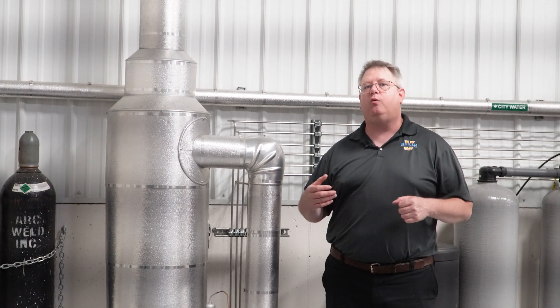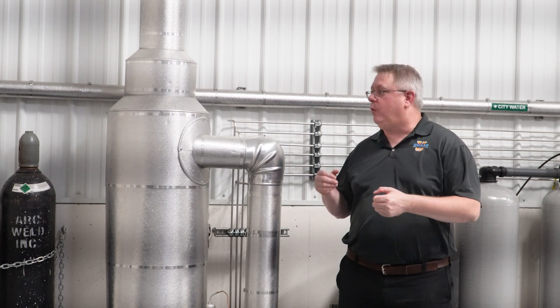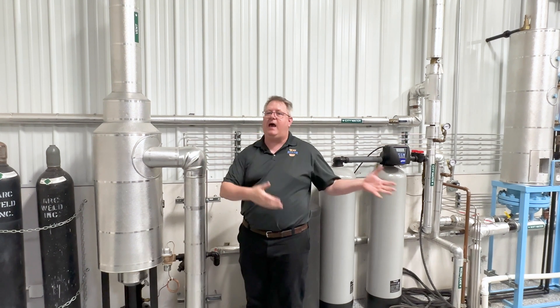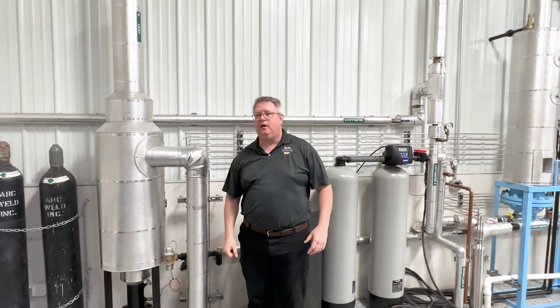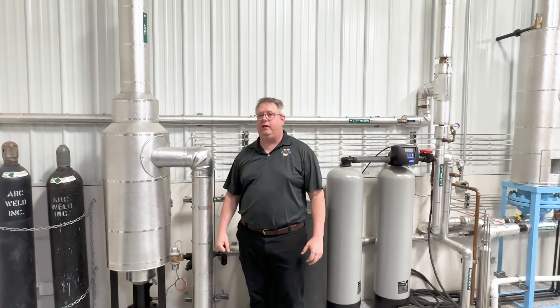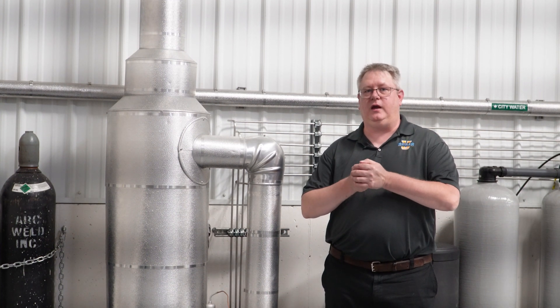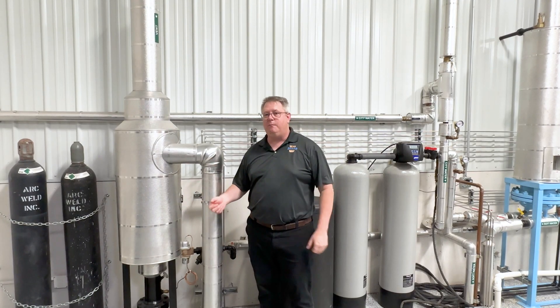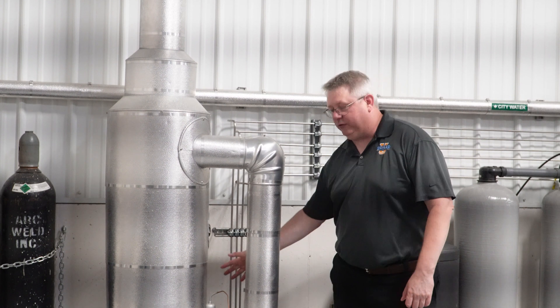There are some industrial sites that have their own wastewater treatment facilities and blowdown pits, so while we might not have a separator in the boiler room proper, that mechanical function may be performed elsewhere in the system. It's really important to comply with local jurisdictions because there are consequences — we've definitely seen melted PVC piping in the floor as a result of somebody not having the cooling water on. Check it out and do your research.